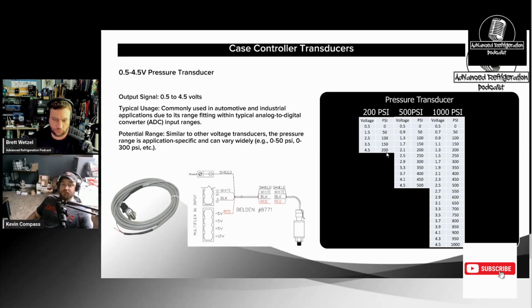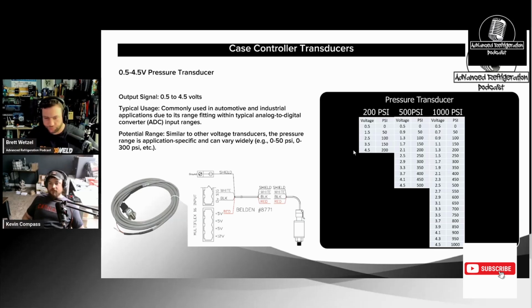At 4.5 volts DC, you should be at 100 PSI. And you could linearly scale that through this. Now, Copeland has a chart, so you don't really have to do this. Danfoss has a chart where you could look at this and say, okay, I'm at 3.5 volts, I should be on a 200-pound transducer, because nobody really uses 100 PSI ones anymore. You should be at 150 pounds, give or take a PSI or two, wherever it is. You should be relatively close to that.